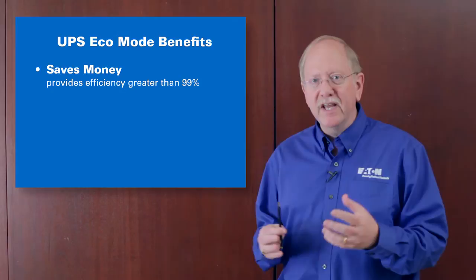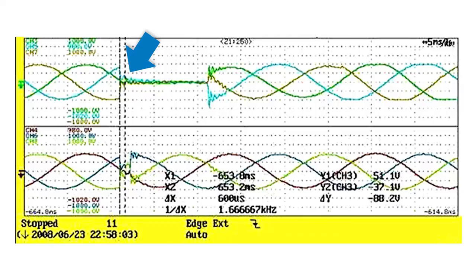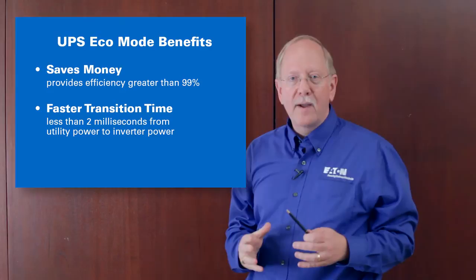By far, the biggest concern with eco mode UPS operation is the observer has trouble accepting that we can, in fact, transition from static switch operation to double conversion operation in less than two milliseconds. So, we use an oscilloscope trace as proof. Here we see the input power disrupted coming into the UPS, and the output power here. At the same point, we do not go to zero volts, but continue to produce a three-phase output. And the transition time from utility power to inverter power is, in fact, less than two milliseconds.